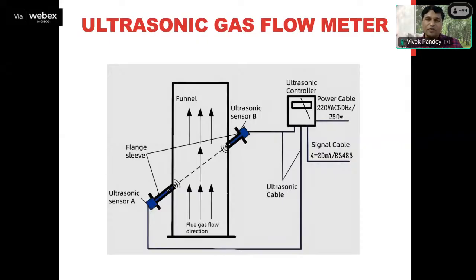As you can see from this diagram, if we want to understand the basic principle of working, in this block diagram there is a funnel where the gas is transferred from downside to upside. There are two ultrasonic sensors connected with this funnel, one on the upper side and one on the lower side. These two sensors are controlled by ultrasonic controllers. The controller operates them so that one sensor acts as a transmitter while the other acts as a receiver, and whatever signals are received are transmitted to the controller, which, based upon those signals and information, gives the quantity of gas.